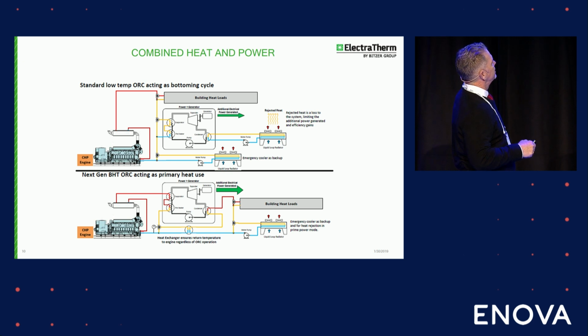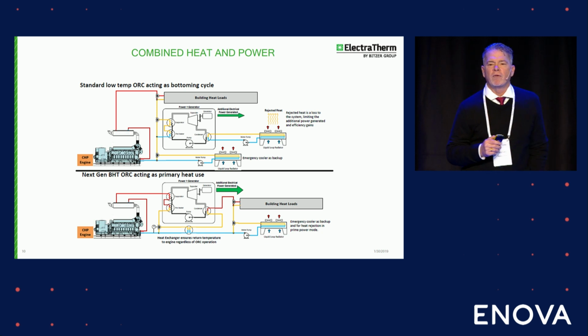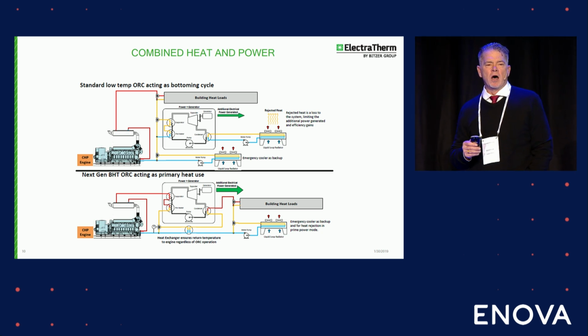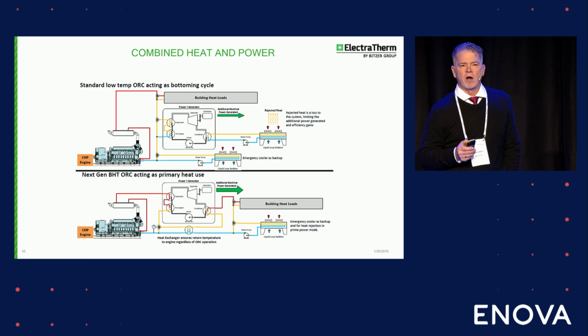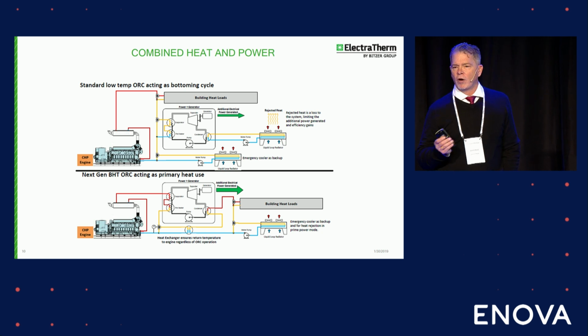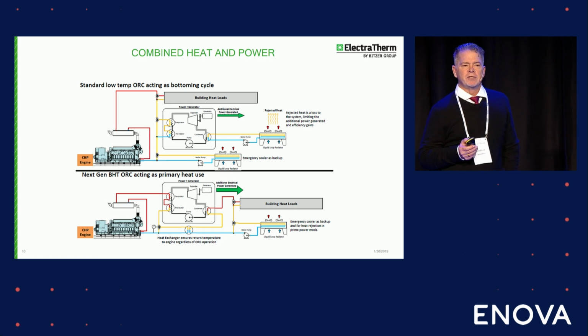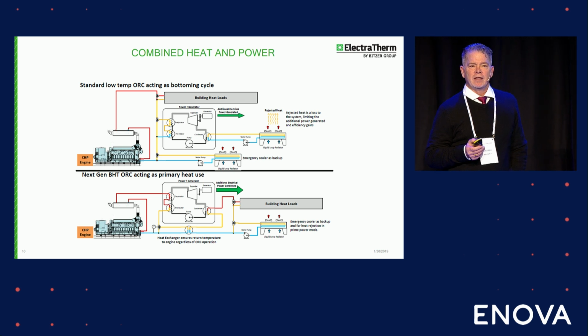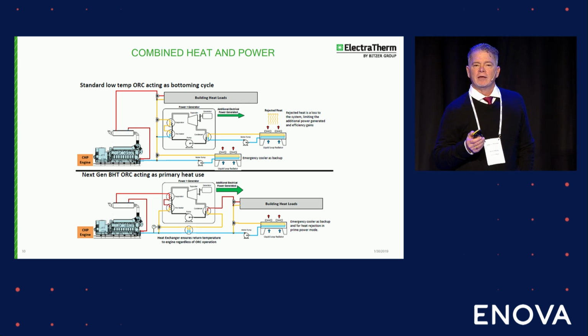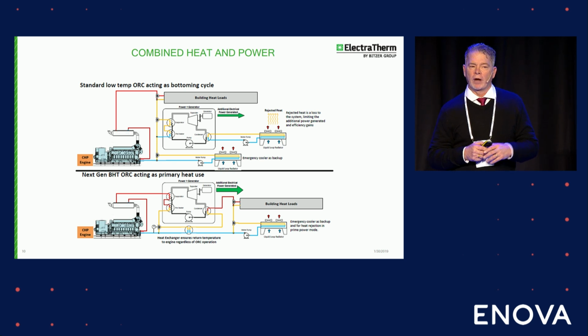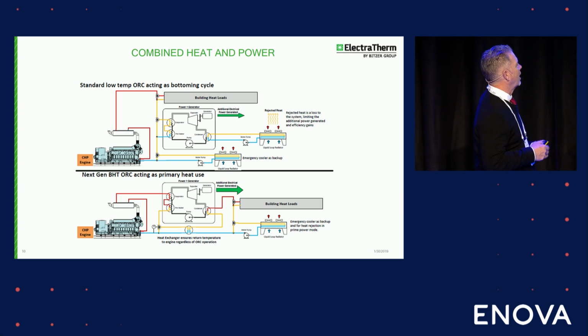Inside the ORC itself, this black line is Honeywell 245 FA refrigerant. It's non-corrosive, non-explosive, environmentally friendly, and has a very low boiling point—about 15 Celsius. That's what allows us to make power at these low temperatures. We've got a low boiling point organic Rankine cycle fluid.